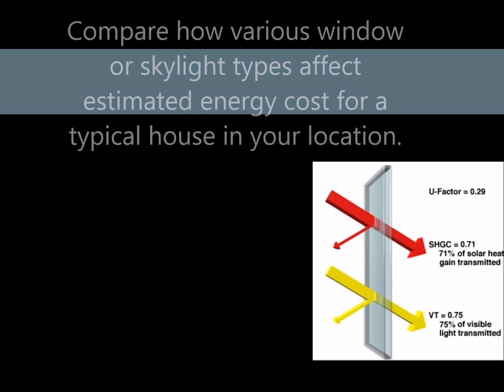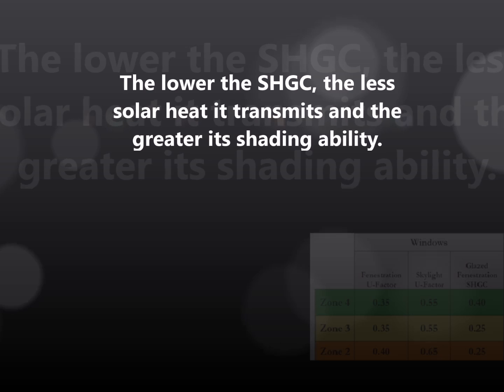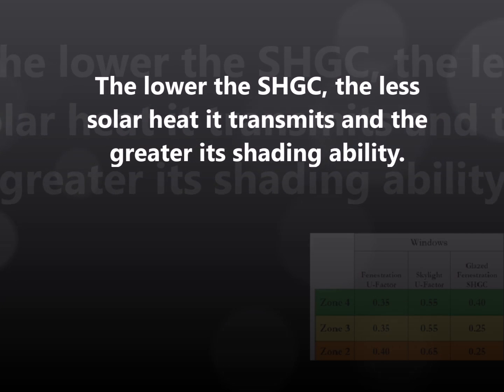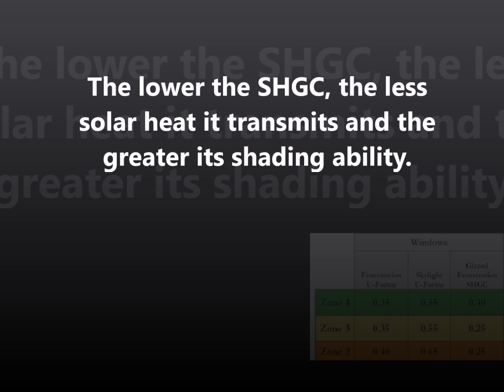Next we look at Solar Heat Gain Coefficient or the SHGC. A fraction of solar radiation admitted through a window, door, or skylight is transmitted directly and/or absorbed and subsequently released as heat inside your home. The lower the SHGC, the less solar heat it transmits and the greater its shading ability. A product with a high SHGC rating is more effective at collecting solar heat gain during the winter.